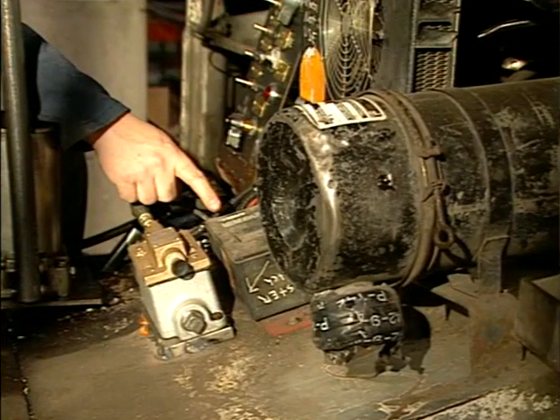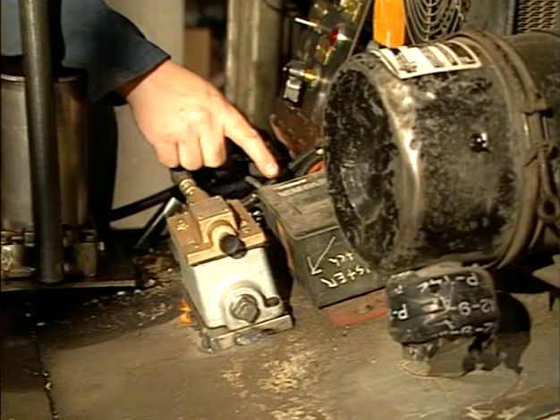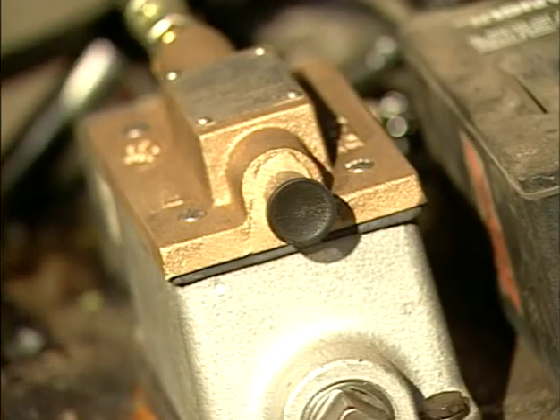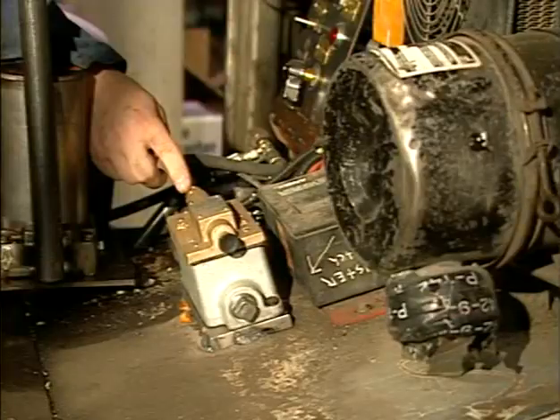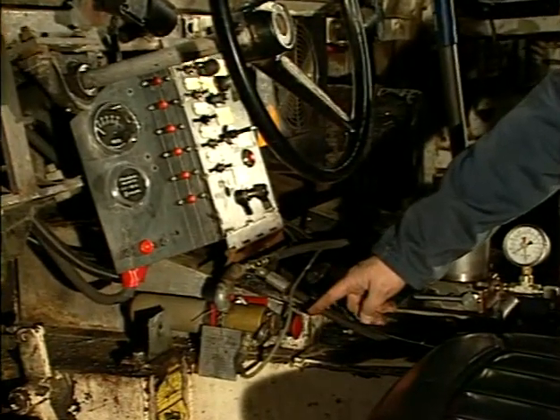Here is the automatic fire suppression system control box. It is independently powered and contains status system indicators; it must be properly maintained and a record kept. This system is set up to provide automatic engine shutdown through a valve that is controlled by the fire suppression system control module and is connected to the fuel shutoff switch. The manual fire suppression system actuator is within easy access of the operator.